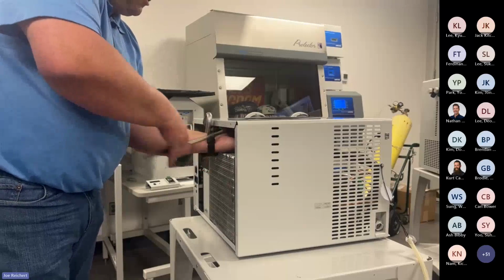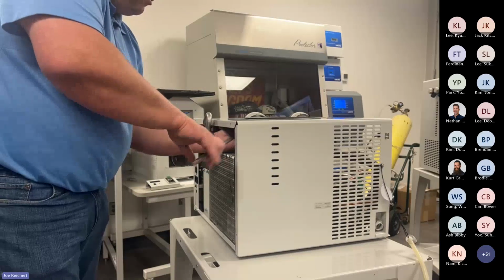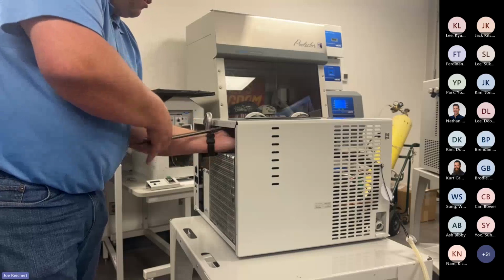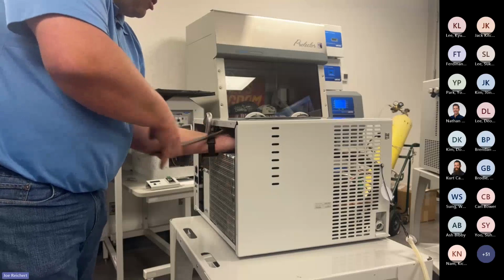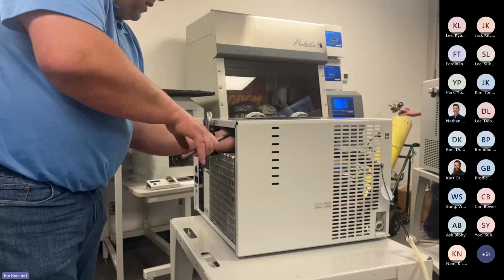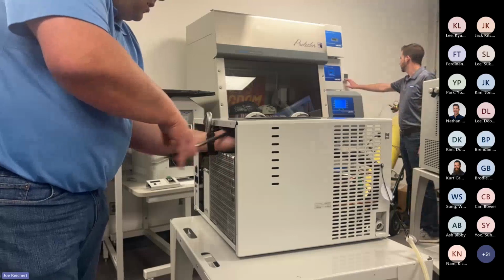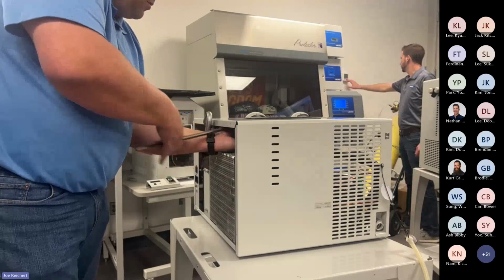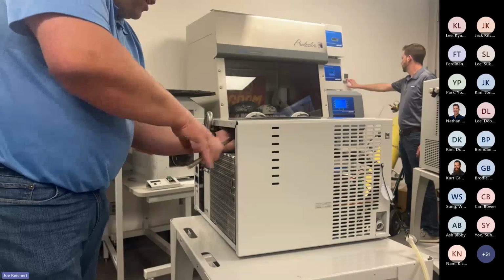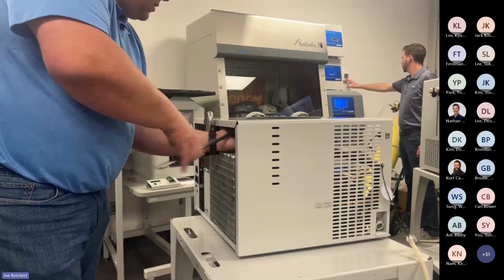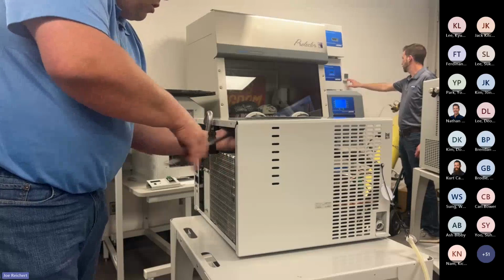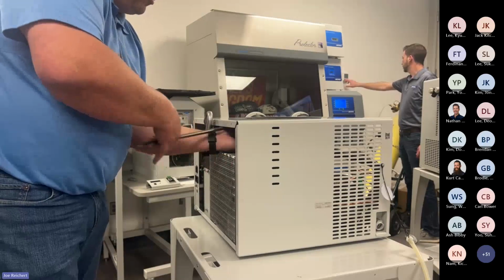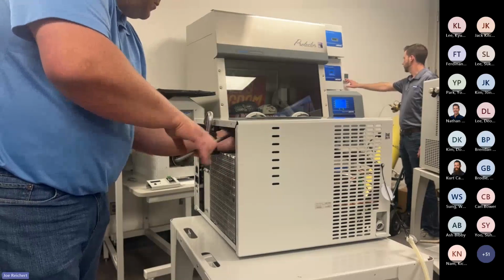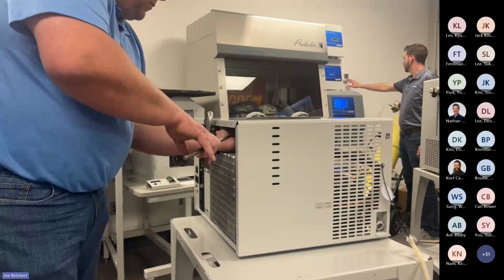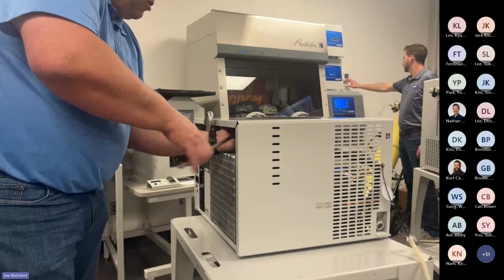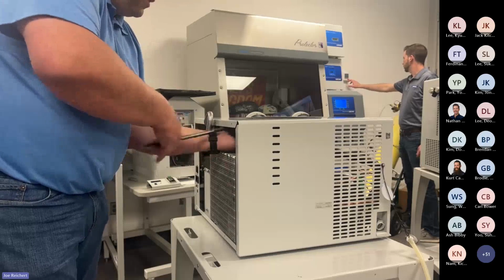So that should help a customer understand how they can still load more samples. A lot of customers get afraid when that number moves or changes and they don't want to add any more sample. But as long as they're doing something like acetonitrile, they're okay to warm that chamber all the way up to minus 60 before they are going to have any issue with bypass into the pump. So they might as well keep adding so they can use the capacity of the unit the way it's made.